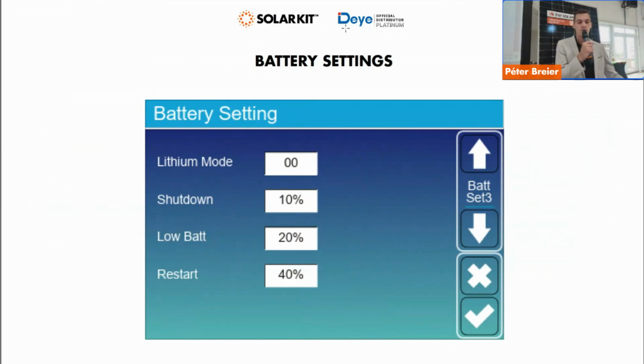Shutdown percentage is a percentage, or an SOC state, after which the batteries will not discharge any current, and low BAT state or low BAT SOC level is a level under which the battery will only discharge current if there is no grid connection. So for example, there is a blackout, then in that case, if the settings are like this on the presentation, you will be able to use 10% of the battery's reserves because it's reserved for blackout scenarios. Restart percentage is the amount until which the battery has to be recharged before it starts discharging again.